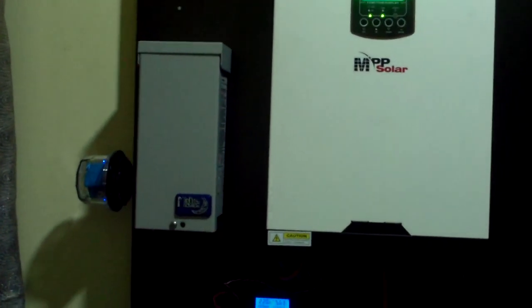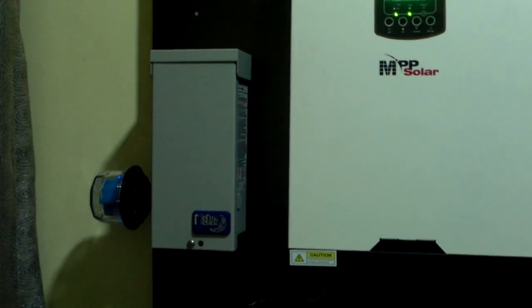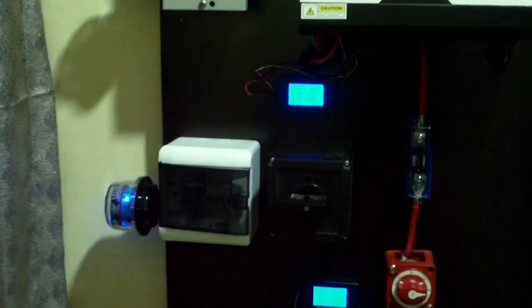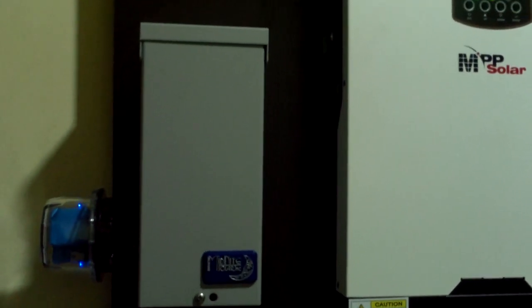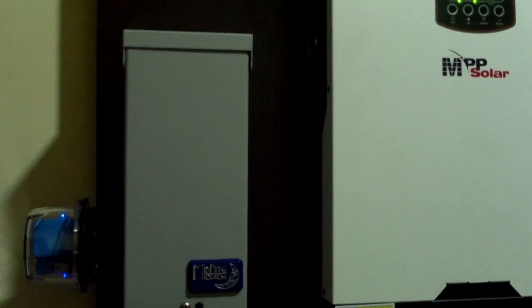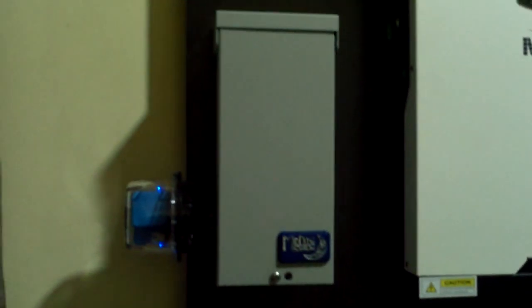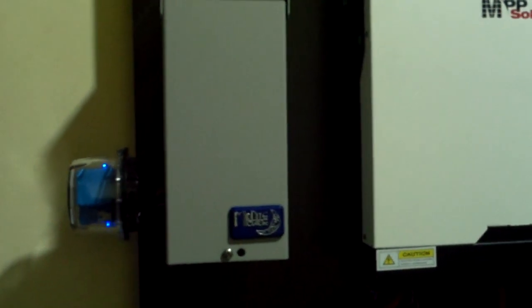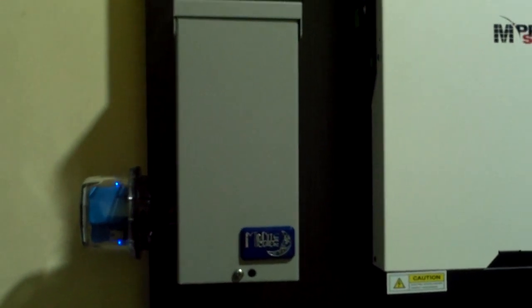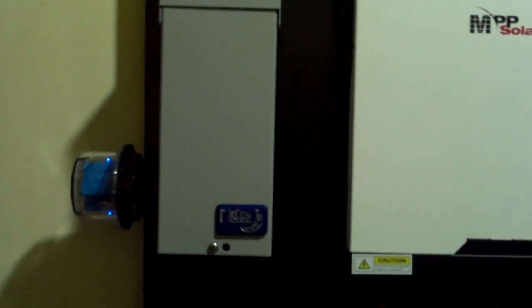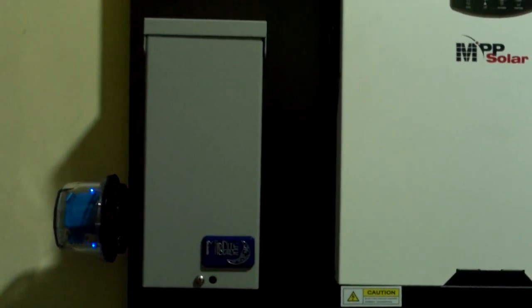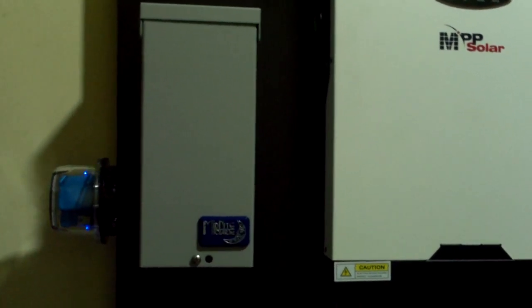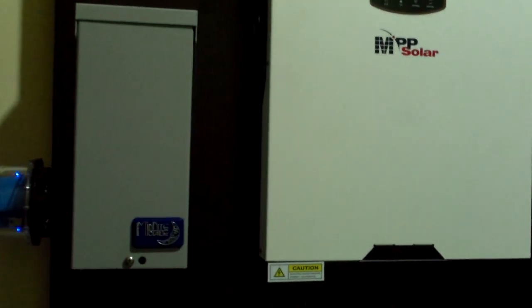The system has a combiner box. It's a long string inverter that takes a maximum of 500 volts DC but nominally works perfectly at 450. We have 10 monocrystalline panels upstairs and the voltage is running at about 430 when it peaks.